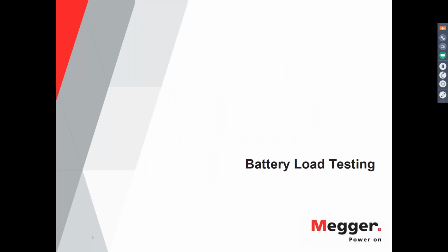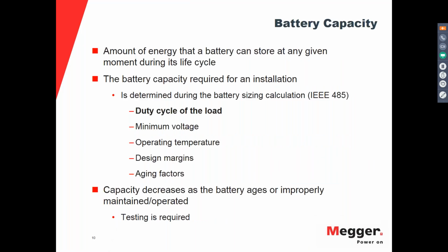So let's get into battery load testing. The first thing to define is the battery capacity. This is the amount of energy that a battery can store at any given moment during its life cycle. The battery is manufactured to meet a certain capacity, defined by the manufacturer. Once the battery starts its life, it will degrade, and that capacity will degrade, and it's going to be losing its ability to store energy. And that's what we want to verify.